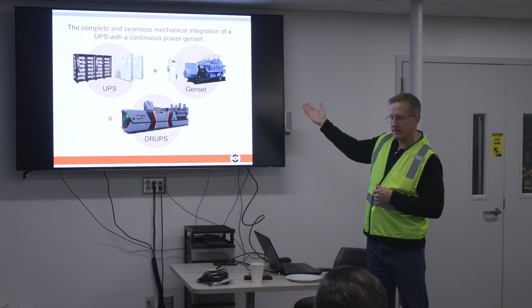All of that gets replaced by our system, our simple three-piece module of a diesel generator, an alternator, and a flywheel, which we'll go into here in detail. All of that static UPS equipment gets replaced by just our one module. So think of all the footprint that would be taken up by a genset and a room full of batteries, now compressed into a unit which is maybe 6 feet by 26 feet.